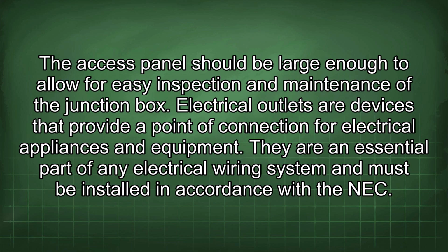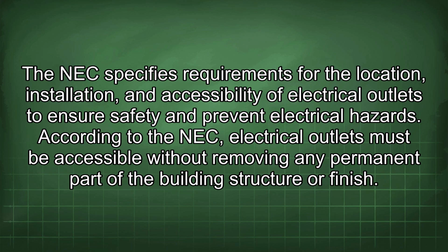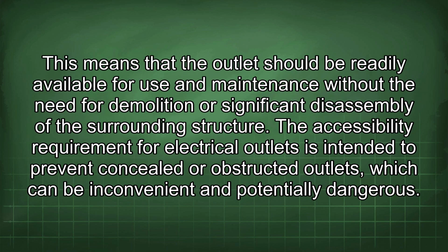Electrical outlets are devices that provide a point of connection for electrical appliances and equipment. They are an essential part of any electrical wiring system and must be installed in accordance with the NEC. The NEC specifies requirements for the location, installation, and accessibility of electrical outlets to ensure safety and prevent electrical hazards. According to the NEC, electrical outlets must be accessible without removing any permanent part of the building structure or finish. This means that the outlet should be readily available for use and maintenance without the need for demolition or significant disassembly of the surrounding structure.